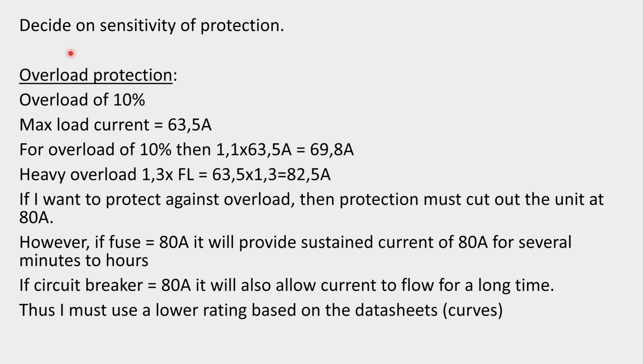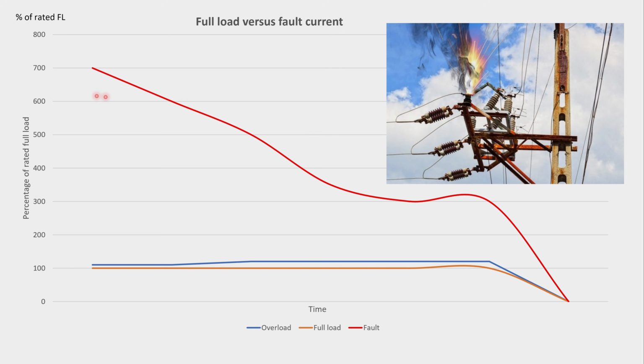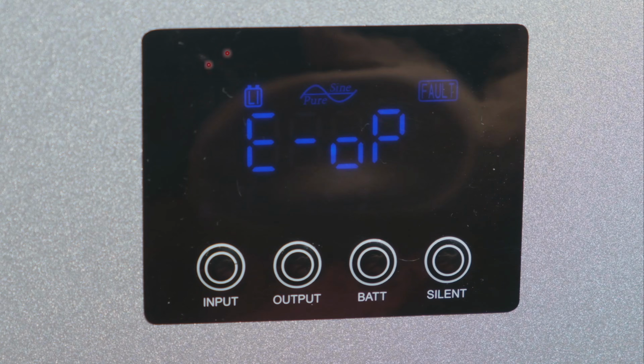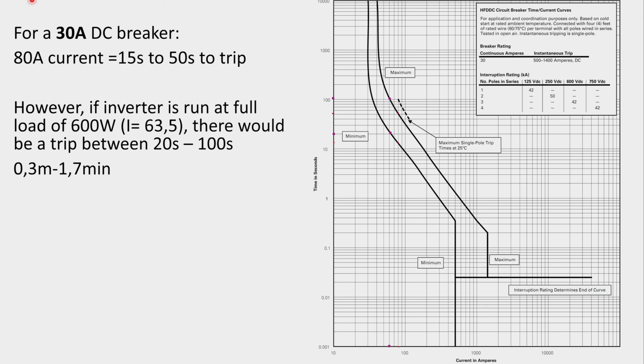I go back to the initial slide and it says decide on what sensitivity you want. Are you protecting for just overload? That means it'll be very sensitive. Just when you overload the inverter, it's going to trip the circuit breaker. Or are we tripping just mostly for faults? Therefore, the circuit breaker will be at a much higher current. So recall that the inverter does have its own internal protection. So I'm not worried about the inverter self-destructing if it's overloaded. I'm not going to use a 30 amp circuit breaker because the inverter's already got its own protection, and I don't want the user to get annoyed with the circuit breaker and remove it.